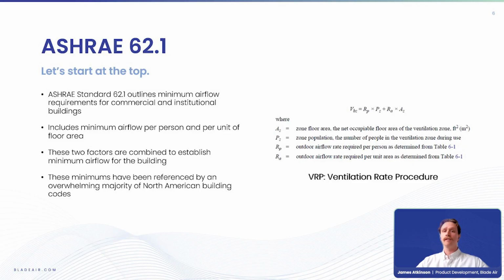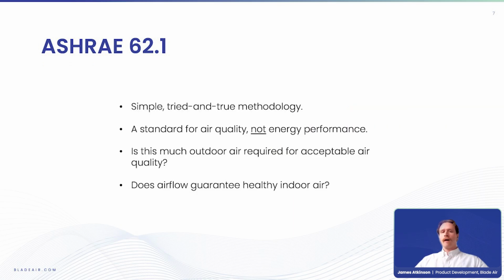And it's that simplicity, that ease of use that's led these to being widely adopted. These have been referenced by the overwhelming majority of North American building codes with very few exceptions. It's easy for an inspector to check, right? They can do the math themselves in a few minutes, make sure that everything's compliant, we're all good. It's not a standard for energy performance, right? This is an air quality standard. So this is a quick way to make sure that people in the building are probably safe, right? You're probably delivering enough air for people to be healthy, happy, comfortable, all that good stuff. But it doesn't really guarantee air quality. It just guarantees ventilation. What happens if you're in, say, a polluted environment, right?